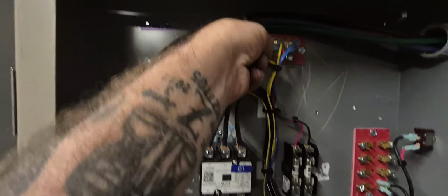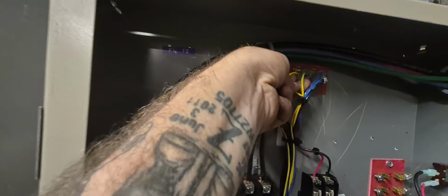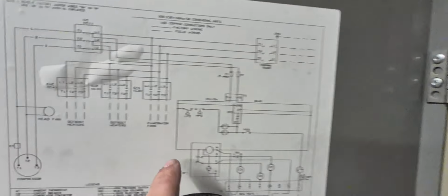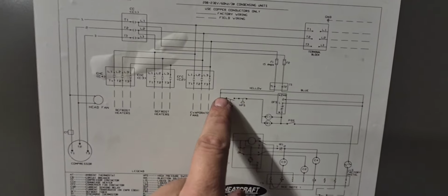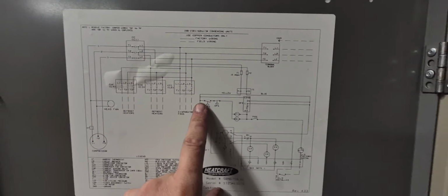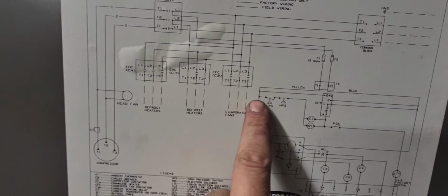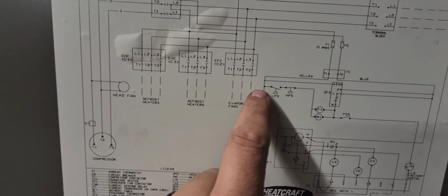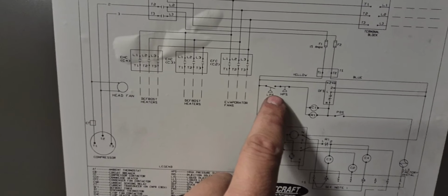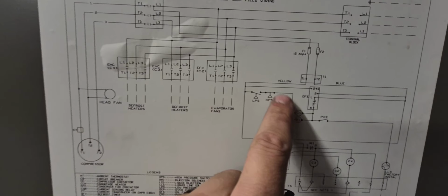Again we'll trace this out. We got one yellow wire, two yellow wire. Come down, catch this. This yellow wire should be going to our low pressure switch, high pressure switch, and then into our contactor.